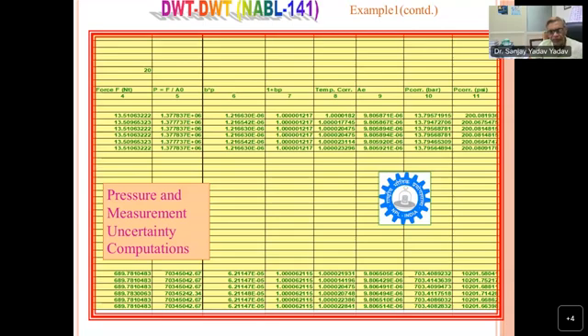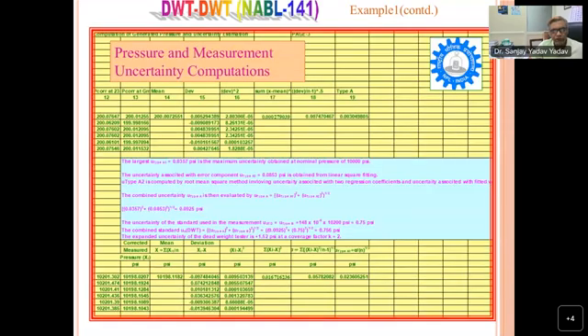Similarly, after the temperature correction and area correction, you can determine the area value, and then force divided by area gives the pressure value. Then you can convert to your desired pressure unit, and then make the correction. Like I have converted pressure into PSI. So after all this correction, you have to make the temperature correction. I have shown in one of my slides at 23 degrees centigrade. Then the manufacturer's G value correction. So then ultimately this is the last corrected value with a nominal pressure of 200 bar.